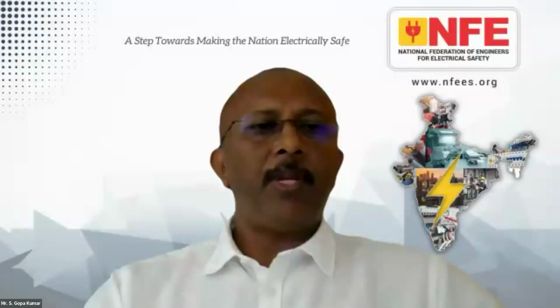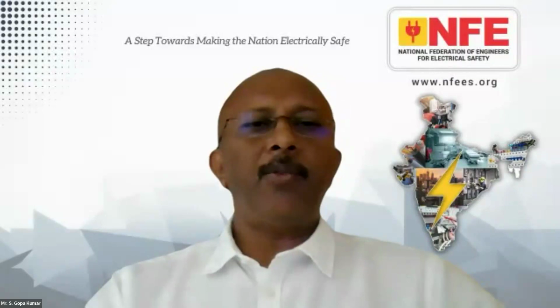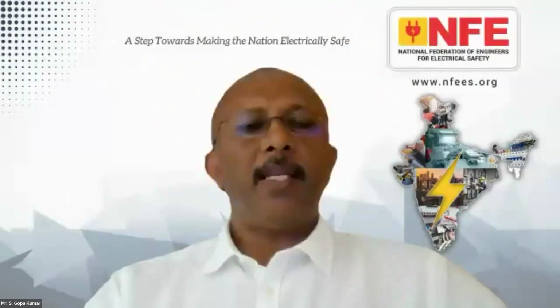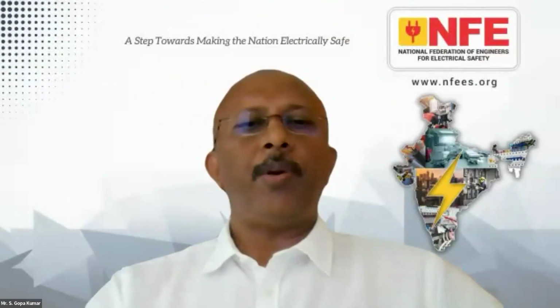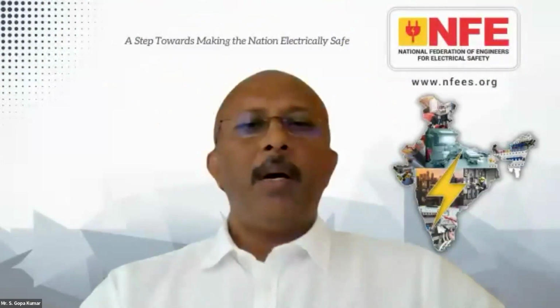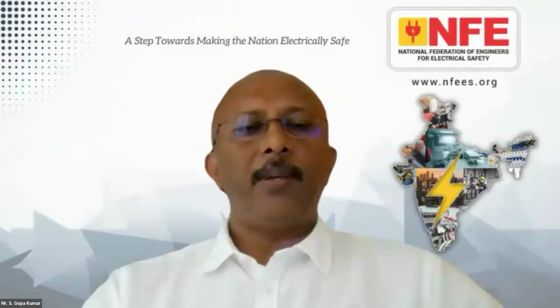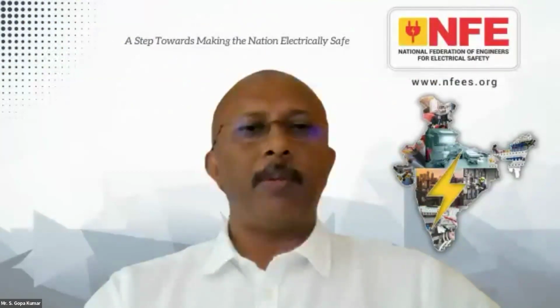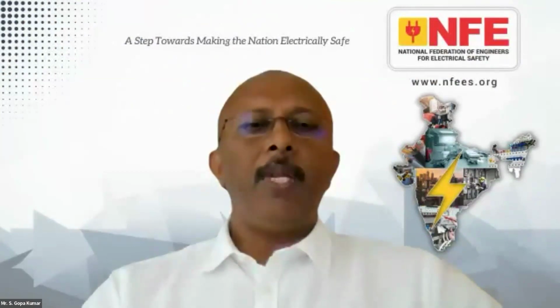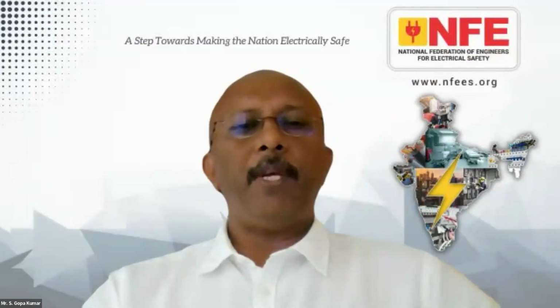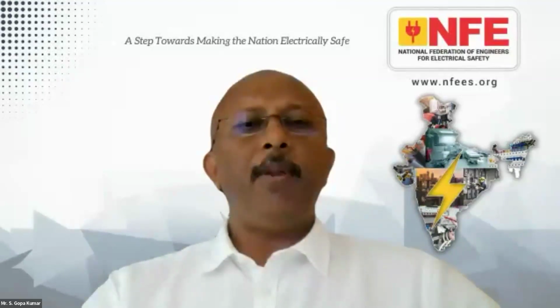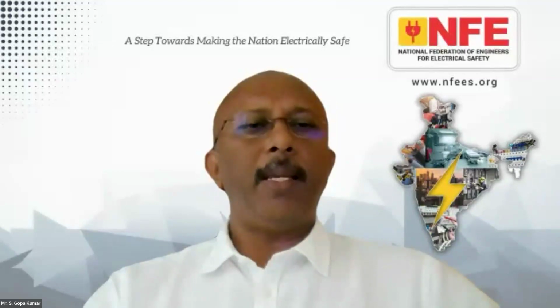There's a question from Mr. Duraiswamy: is IMD, insulation monitoring device, mandatory for Group 1 and Group 2 locations, and is there any NABH guideline? Per the National Electrical Code, yes, in Group 2 location, not Group 1. In Group 2, medical isolation, or IMD, is mandatory. Actually it's not just IMD, it's the medical IT system, which includes the insulation monitoring device, so we must be careful with the wording. In Group 1 location, if a supply failure or single fault in any equipment could cause ignition, then that location also needs a medical IT system.